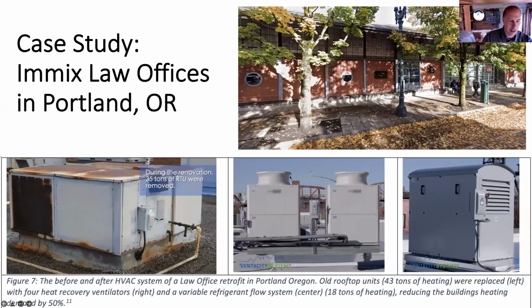This is a VRF, so variable refrigerant flow. It's sending refrigerant in little tiny pipes around the building in a variable amount, with little computers to control how much it sends. So they put that in - that's 18 tons, so less than half. What they put in were heat recovery ventilators, so they recaptured a lot of the heating and cooling as they're doing the ventilation work. That's how they cut the tonnage in half - they put in some efficiency, just getting the heating and cooling back instead of having to make it new.